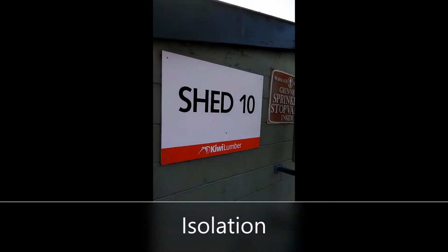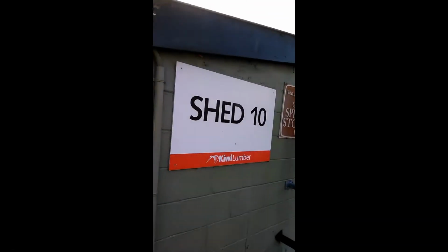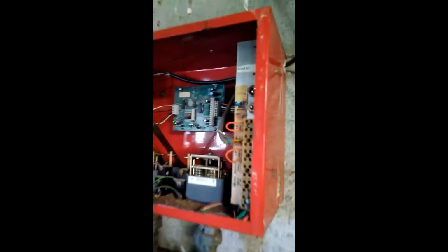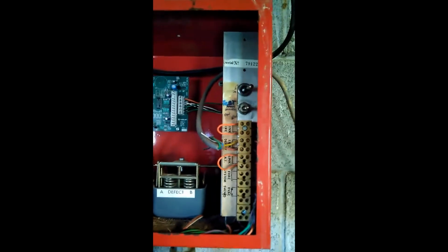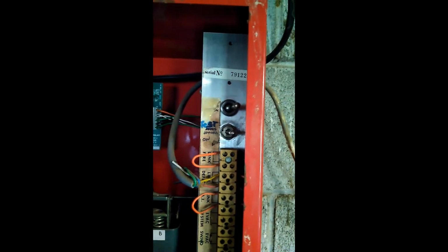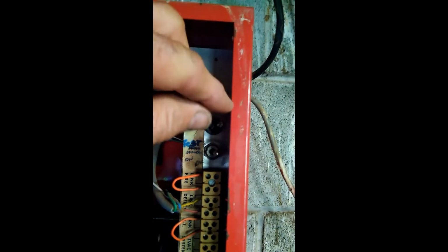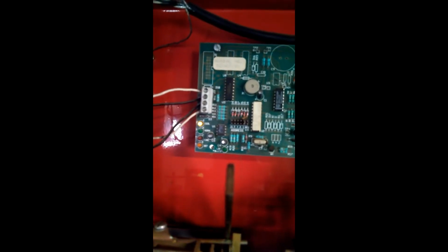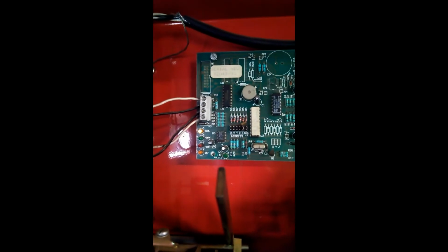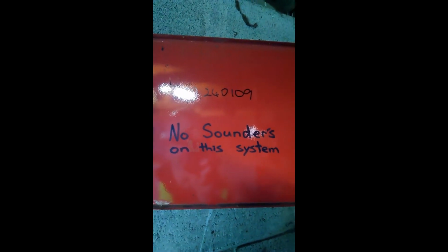We're at Kiwi Lumber, going to show you how to isolate and drain down the sprinkler system. The DBA has only got two switches, one's a test and one is normal, so you isolate that. The SGD board will go to isolate, and it's written up there, there's no sounders on the system.